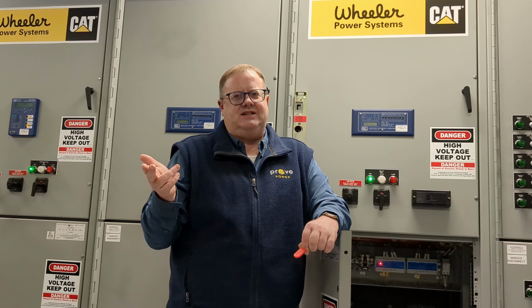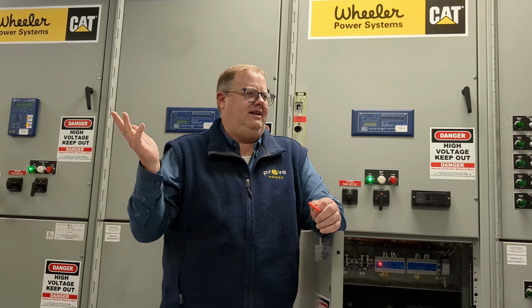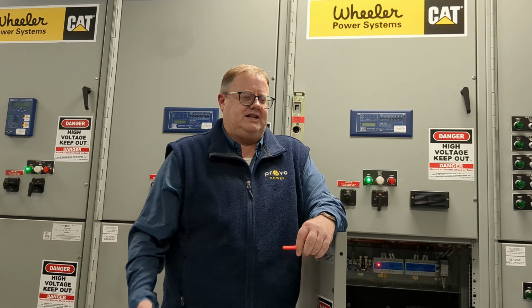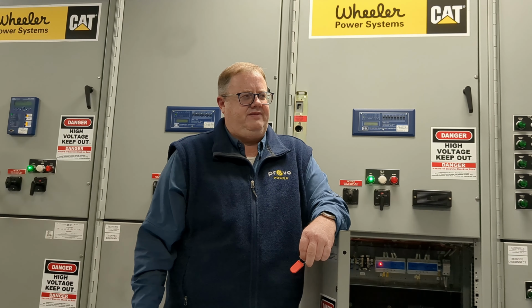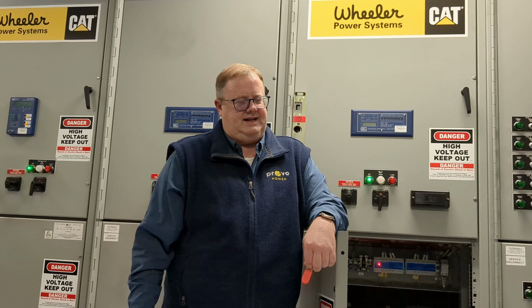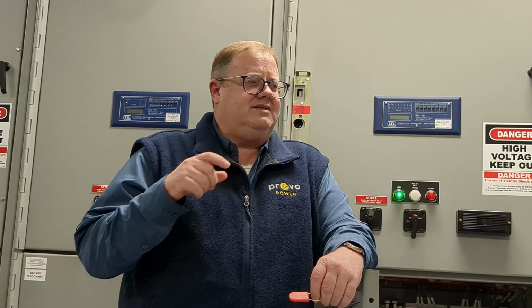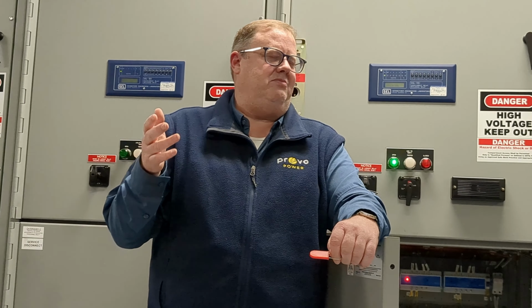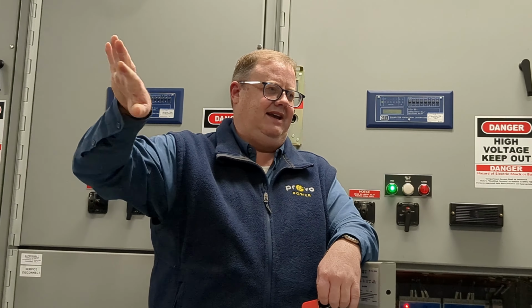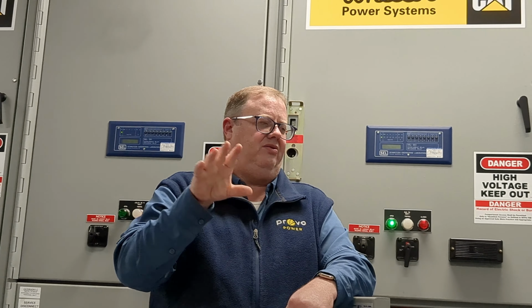So that's why sometimes you see the lights blink off and on, and then the power just stays on. That's what you're saying, the fuse. You do that, and you don't have to blow a fuse. Yes. Sometimes you do a fuse blowing scheme where you would program the relay to hold in the fault longer, blow the fuse on the first one, isolate it, and then open up and close. The first one we want to eliminate temporarily, try to get back on, and then blow the fuse.